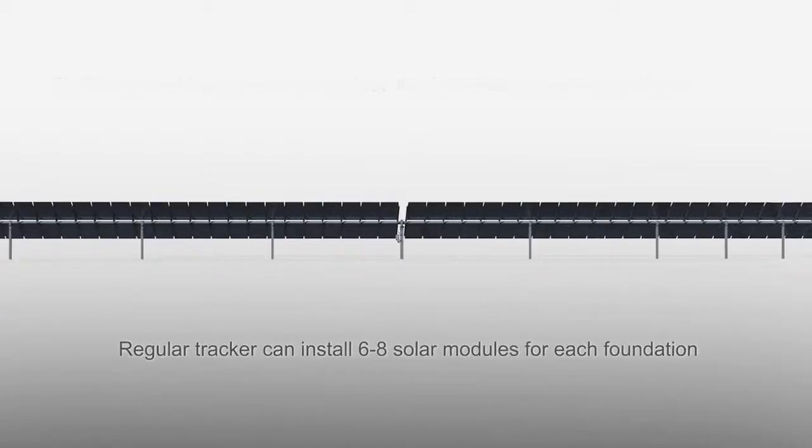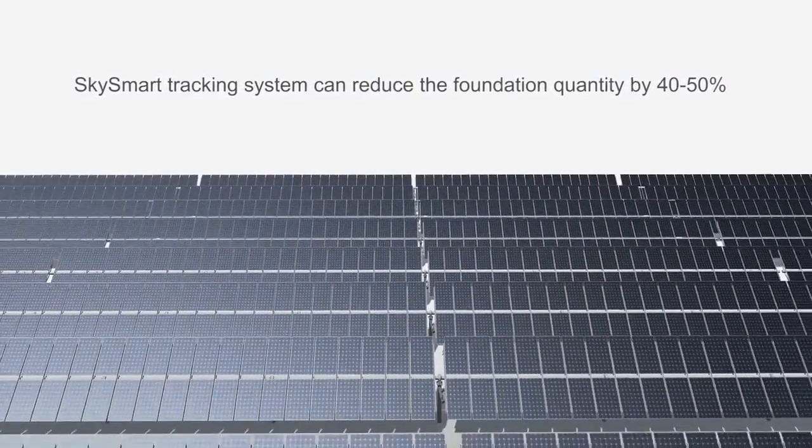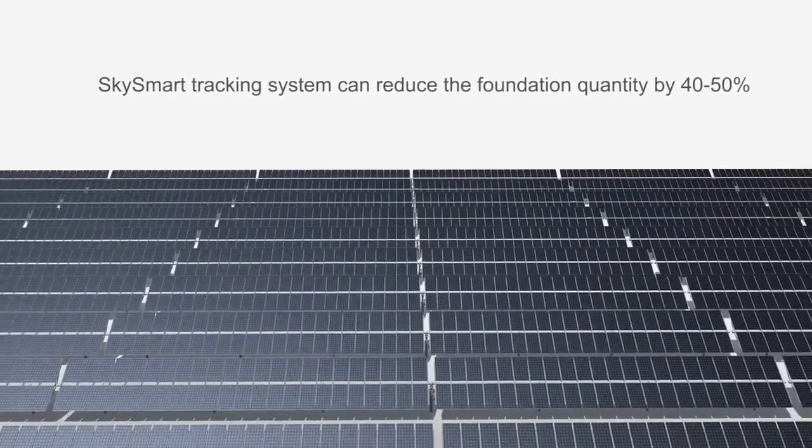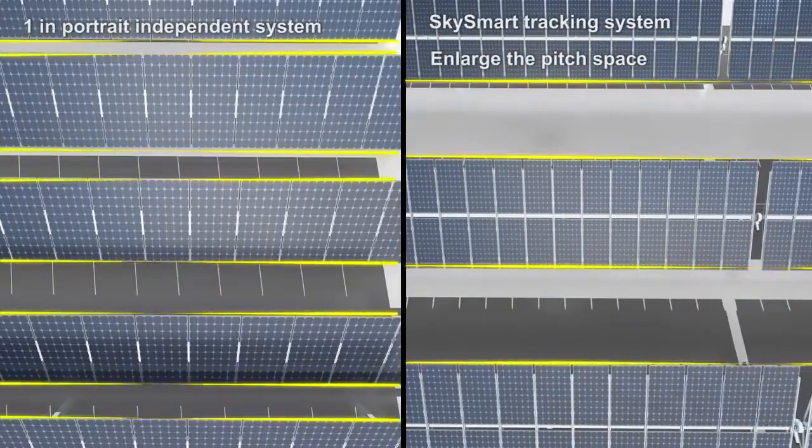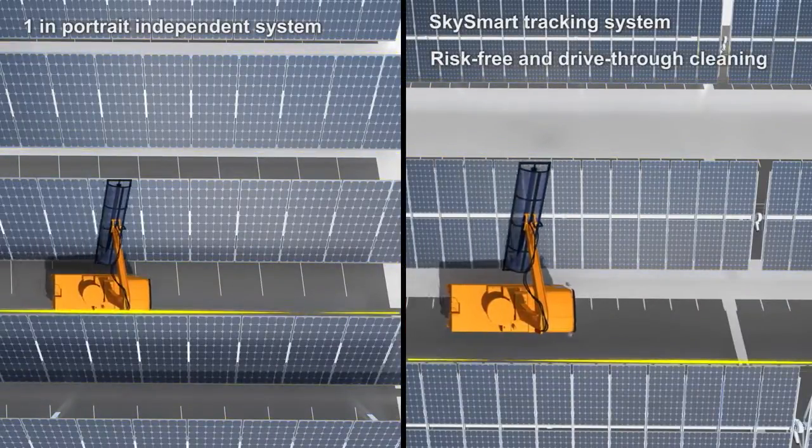Take 385 watt solar module for instance. One megawatt project only needs 200 foundations. This can efficiently reduce the installation and land cost. Two rows of solar modules will double the pitch space and allows the cleaning machine to drive through freely.